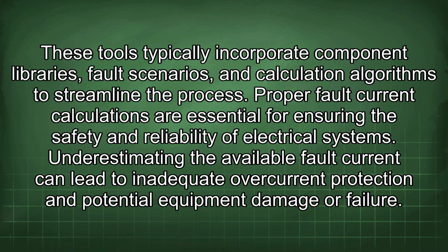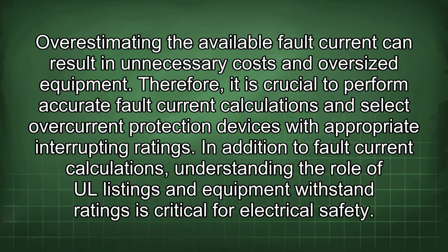Underestimating the available fault current can lead to inadequate overcurrent protection and potential equipment damage or failure. Overestimating the available fault current can result in unnecessary costs and oversized equipment. Therefore, it is crucial to perform accurate fault current calculations and select overcurrent protection devices with appropriate interrupting ratings.